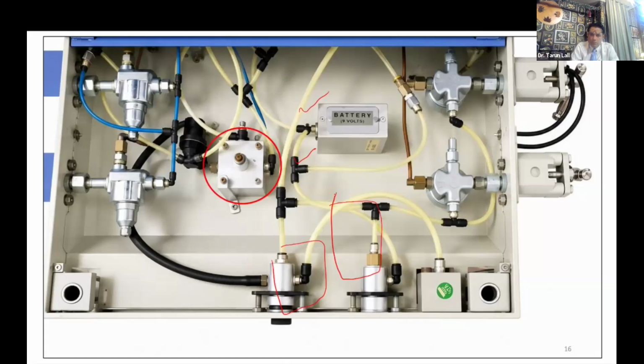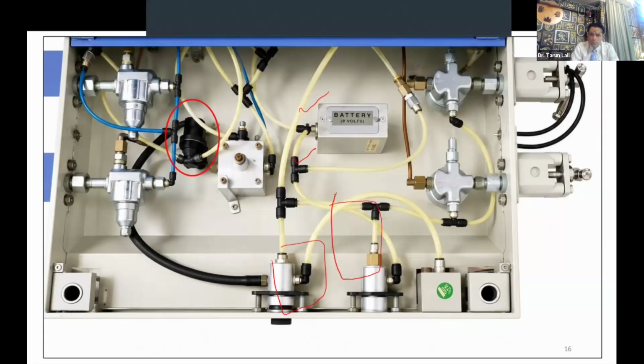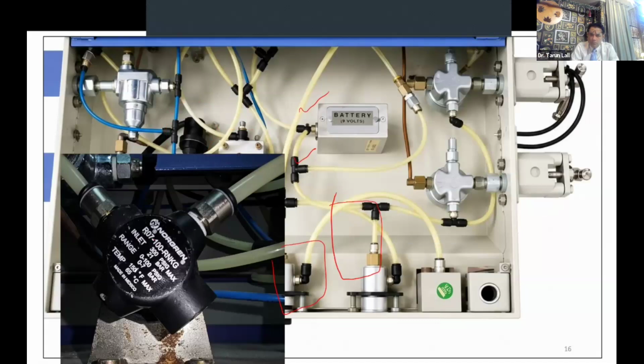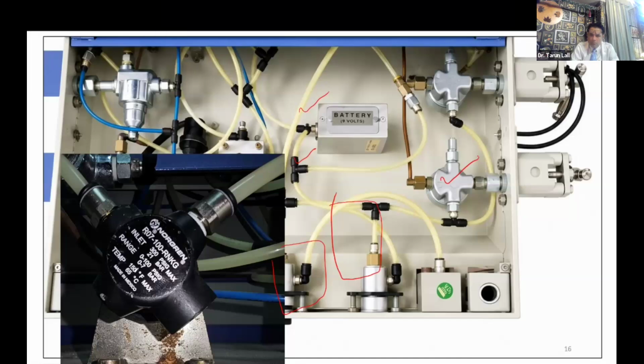Third thing we said is this black plastic thing. So again, we open it and turn it around, and you see that it has an inlet pressure range from 0 to 100 psi. So this is a second stage oxygen pressure regulator. The first stage pressure regulator has brought down the pressure to maybe 40 to 60 psi. Beyond that it is further reduced so that by the time the oxygen reaches the low flow system, the pressure has already come down sufficiently. So this regulator will reduce the pressure to around 10 to 20 psi.